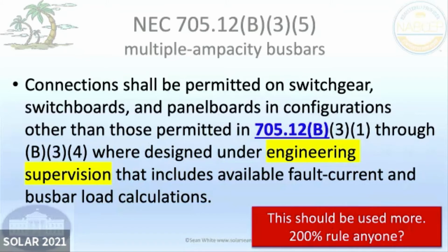I'm just saying, instead of the 1.2 multiplier, if you had a 100 amp bus bar and it was fed by 100 at the top and 100 at the bottom, and you had 200 amps of loads in the middle, you'd have 0 amps in the middle and 100 amps on each side. So you'd never have 200 amps running through that bus bar all at one place. There's an argument for the 200% rule, but there's an argument against it, that you still have too much heat on that thing, because it could generate heat. So under engineering supervision, you can do things.